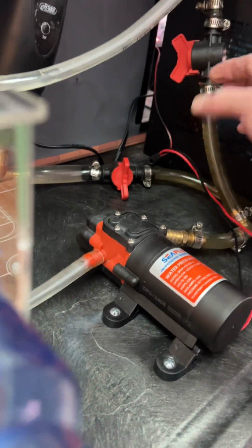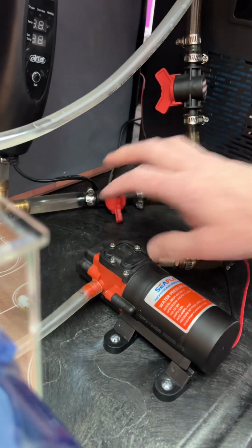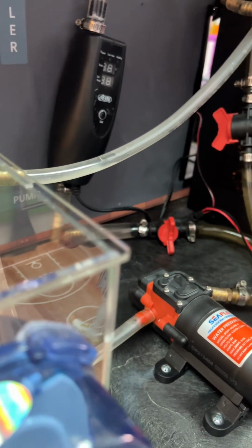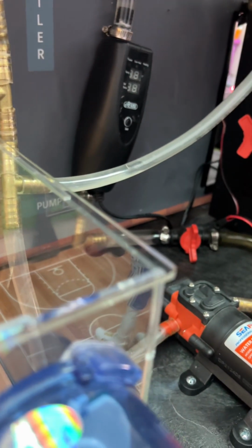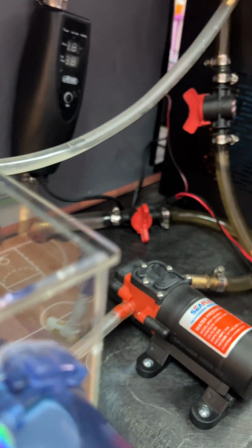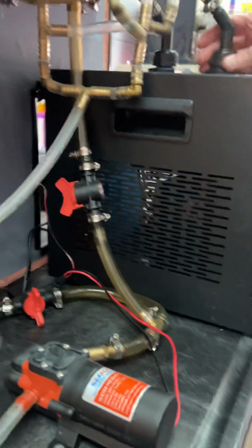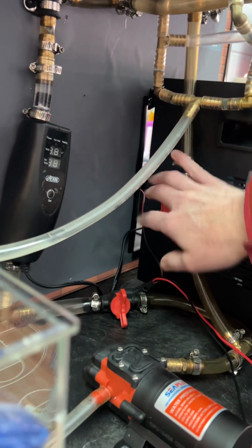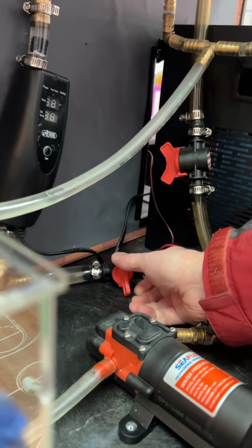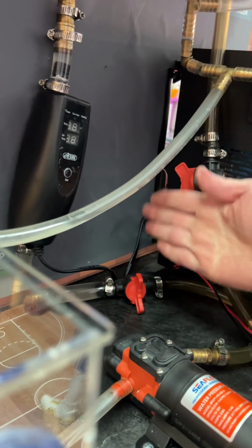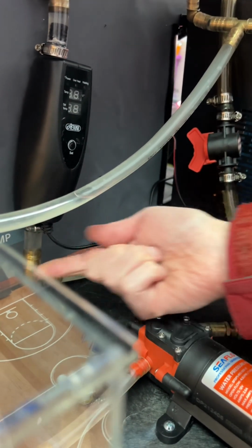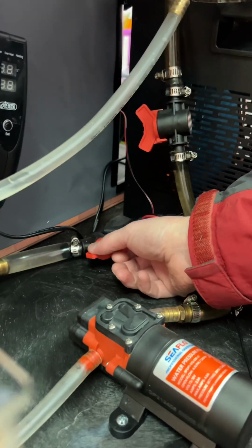For this, the valves are all operated manually, so we need to turn them. When we are operating, we need to decide which mode we're in. We don't want to run heat and cool at the same time. It's not going to work well, and it's not going to be great for the chiller or the heater to have hot or cold water running through the wrong thing. So we want to isolate it, and those valves are here to open or close. Simple thing on the valves: if the valve top is perpendicular to the pipe, it is closed. If it's in line with the pipe, it'll let water flow through it.